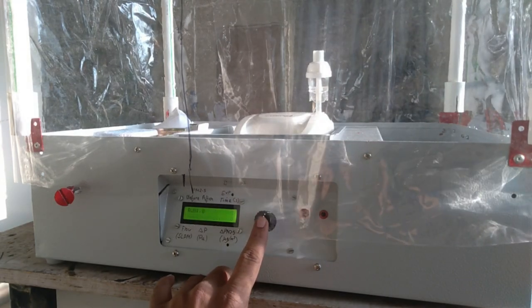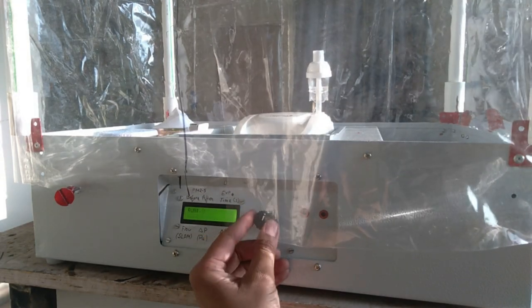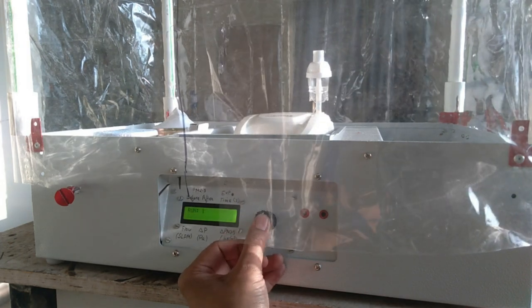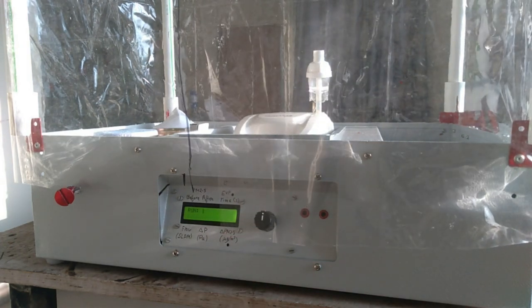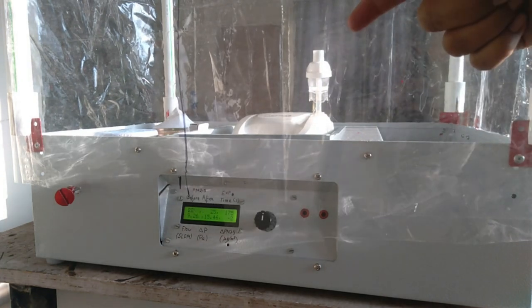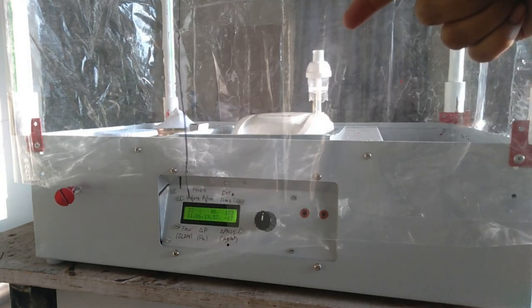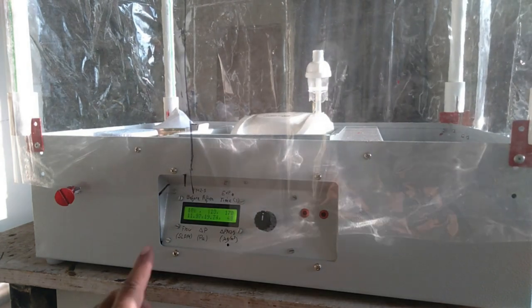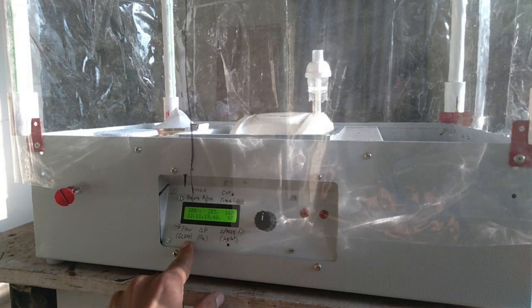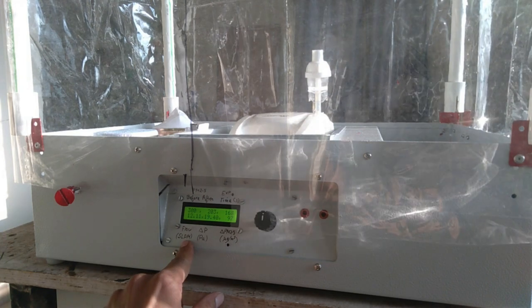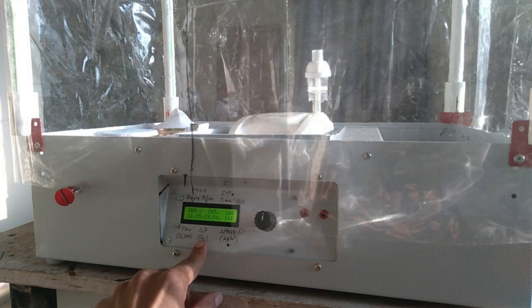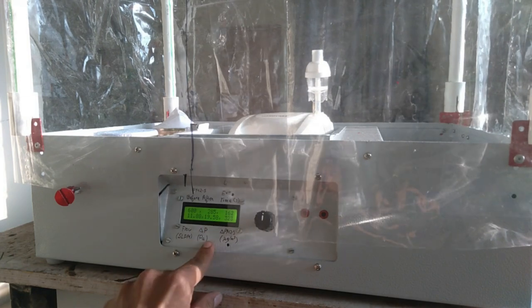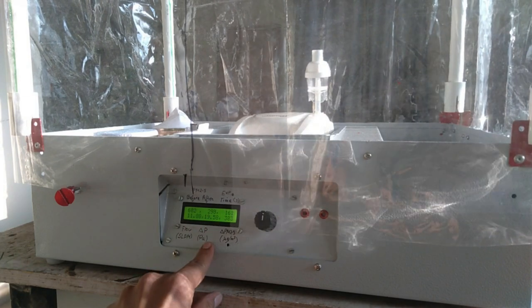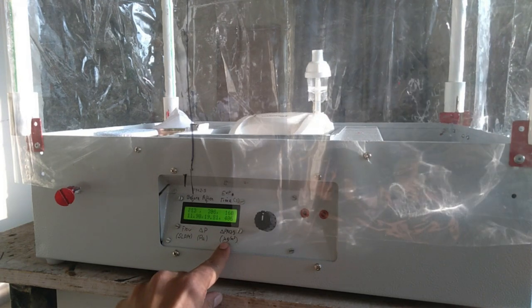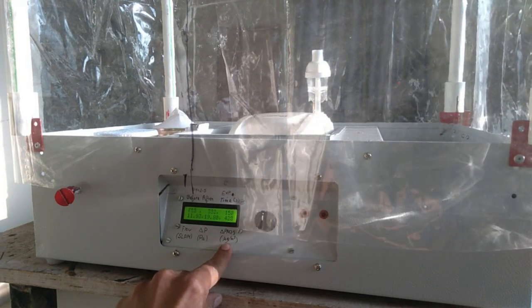When we switch on the machine via the rotating knob control, the fan and the nebulizer start. You can see the nebulizer emitting aerosols that contain salt particles that will eventually become PM 2.5 particles. On the LCD screen on the bottom left, you will see the airflow rate through the masks, which is in standard liters per minute. In the bottom middle, you will see the pressure drop across the mask in pascals. You will see the difference in the PM 2.5 levels before and after the mask.